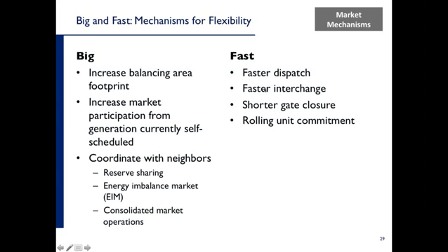We can move to faster dispatch and interchange and the shorter gate closure, all of these things that we saw before, in addition to a rolling unit commitment. It may be that rather than just doing commitment once each day at 12 o'clock noon for the next day, we may decide that it's advantageous to do unit commitment maybe every 12 hours or maybe every 8 hours, maybe every 4 hours.